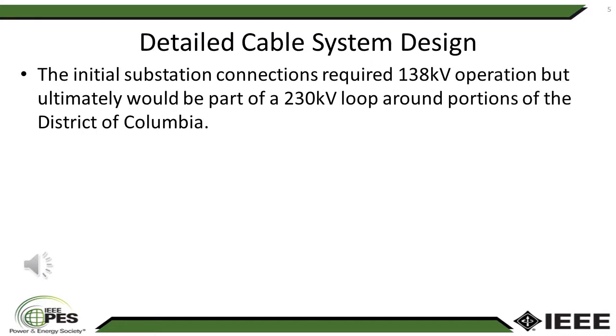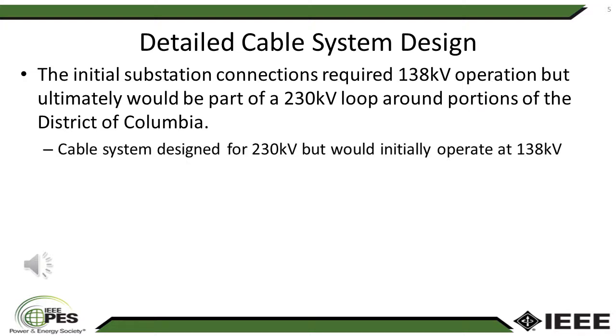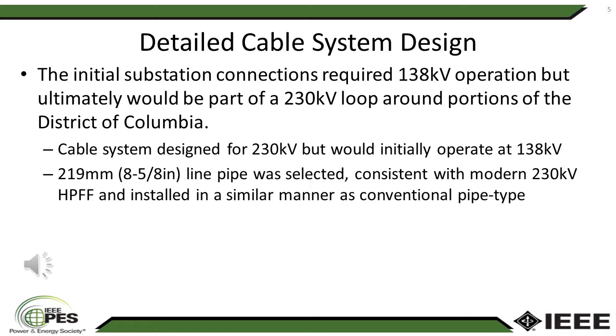Initial substation connections required 138 kV operation, but ultimately would become part of the utility's 230 kV loop around portions of the District of Columbia. 230 kV class cable and accessories were selected, but would initially operate at 138 kV. Consistent with the 230 kV pipe-type system of the time, 219 mm or 8 5/8" line pipe was selected.